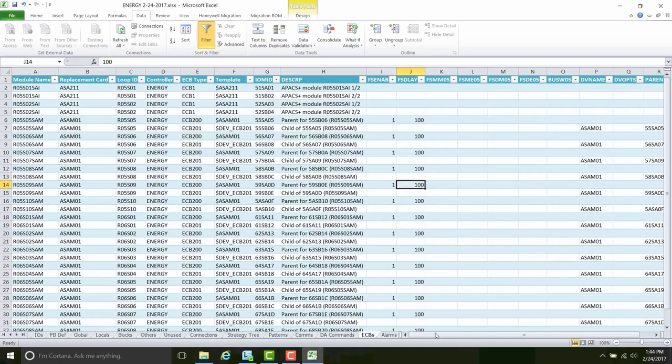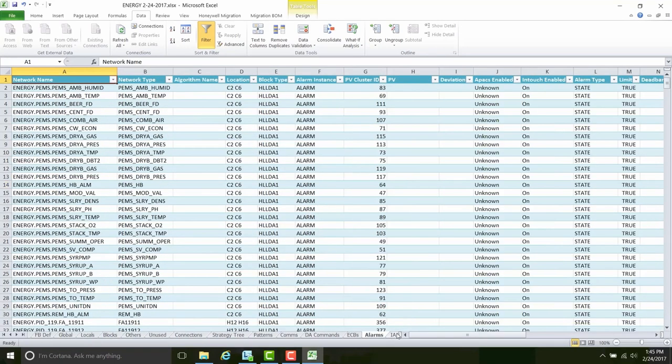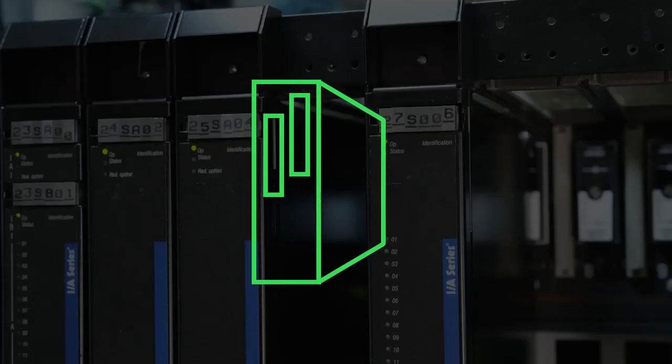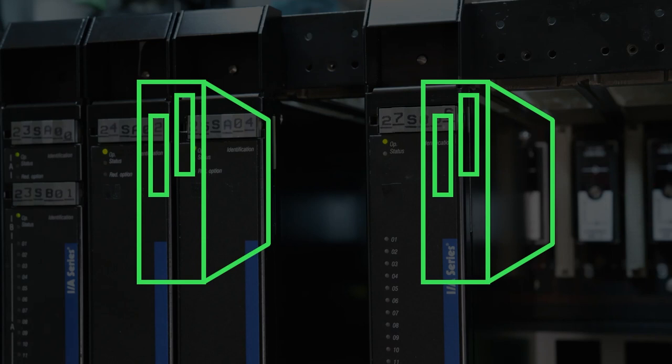Nothing is lost. Now you've got all your alarms. We capture all the alarms that are present in the system, analog, PID, and digital. We synchronize the alarm with human-machine interface software and merge the alarm groupings, alarm priorities, and alarm descriptors. The goal is to ensure that the new system mirrors the critical features of the old and reduce duplicate entries.